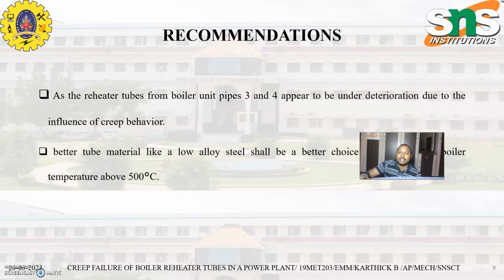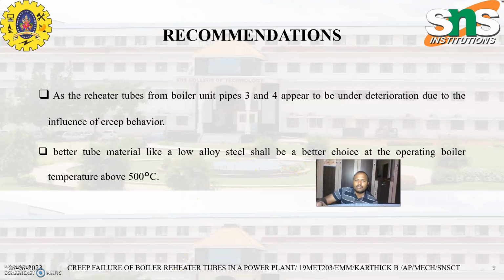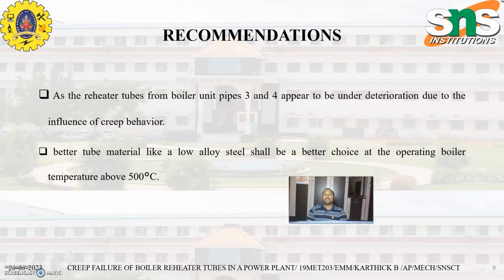Here the recommendation is that the reheater tubes from boiler units 3 and 4 can be under deterioration due to the influence of creep behavior. So we have to change the particular reheater tubes because they undergo creep, and they should be periodically monitored to avoid creep failures in the future. A better tube material is low alloy steel, which is a better choice for an operating temperature of about 500 degrees Celsius.